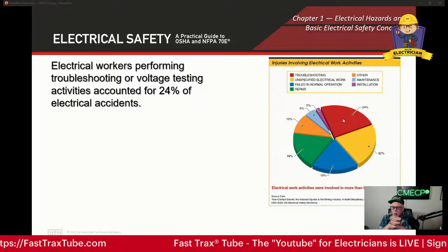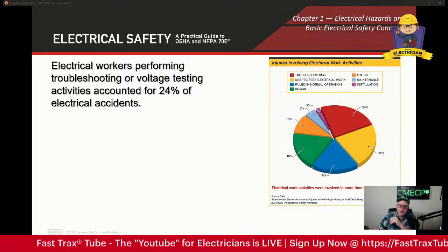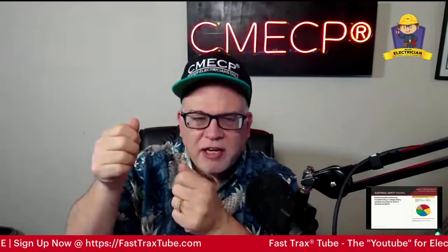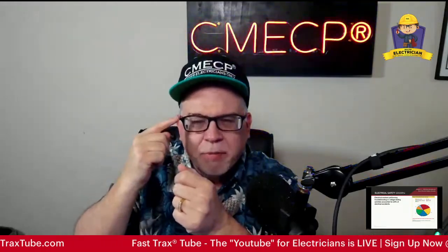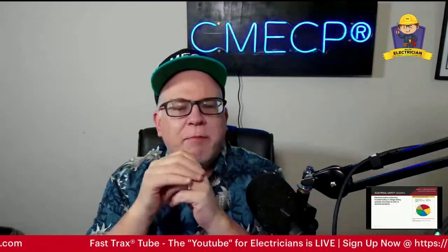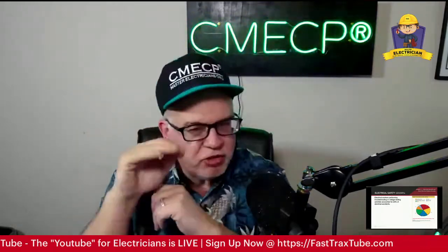Those should be the ones where you really take precautions, proper PPE, making sure you're wearing gloves when you're testing, eye protection even during the testing phase. So again, when you're going into an electrical panel, even in residential applications, we all want to be super people, we all think it'll never happen to us, and I hope it never does. But when you start sticking your meter in there and testing things, really have eye protection on. Now we've gone a long way in the electrical industry, we protect the buses and services, put protective covers on so the live part is up there. But that bus is live unless you turn off the main. If you turn off the main and you're working below, it's kind of hard to troubleshoot, right? Got to be live to troubleshoot. So as far as 70E is concerned, when you're working on equipment like that, you need certain levels of PPE, depending on the risk assessment.